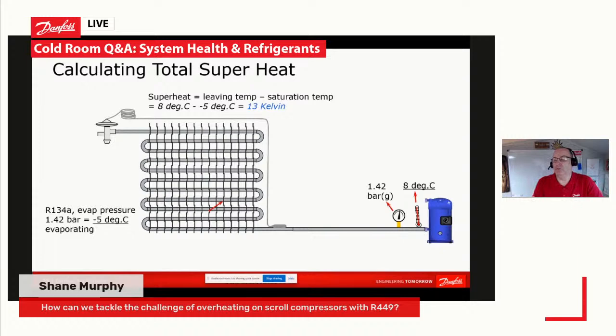So basically 2 things. 1, fit a discharge gas thermostat as a safety. Don't rely on your HP switch or your LP switch, because you will kill a scroll much quicker than those can react. So discharge gas thermostat is the main one, but also, correct commissioning on the system. Make sure that you've got your total superheat. Okay. So I hope that answers that one, Shane.